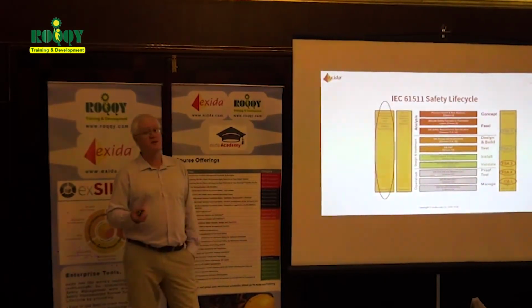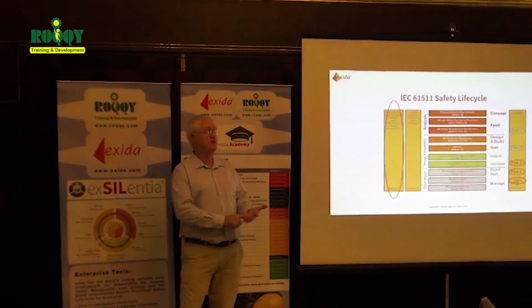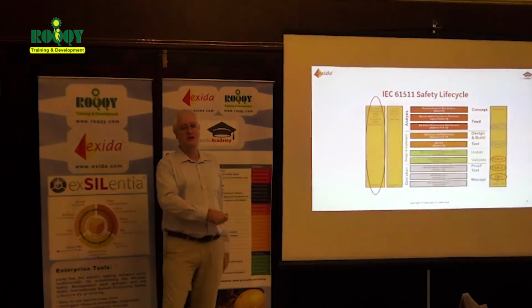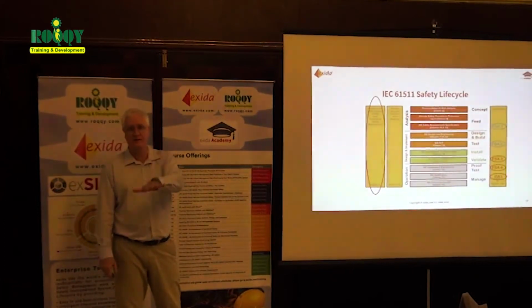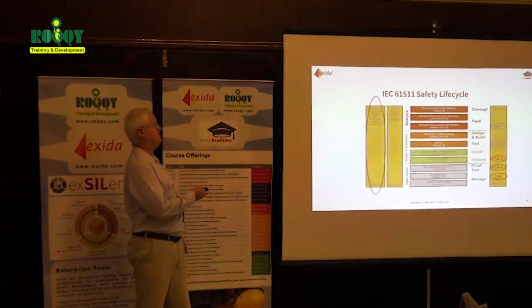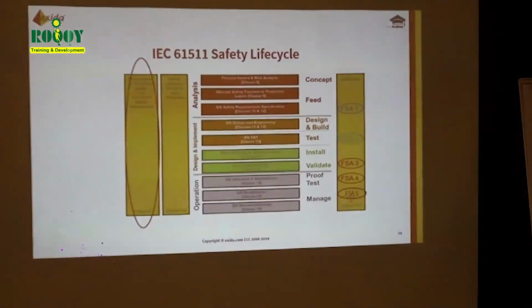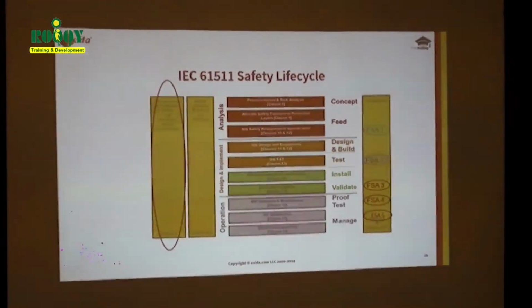So the problem comes, and I've often been called to site, please come and do an FSA 3. We're waiting to start. Our pre-startup safety review is saying, quickly do an FSA 3. And we want to start on Monday, and I get called on the Wednesday. So I go to site, open the books, and I say, where's your FSA 1? We haven't done it. Okay, let's start at the top. So 2 weeks later, I'm still going through everything. And they're all very angry with me. And I say, don't be angry at the messenger. You should have been doing this. The standard prescribed this to be done at this stage. It should have told you to do it. Okay. So it is a structured way of managing people, managing your projects.